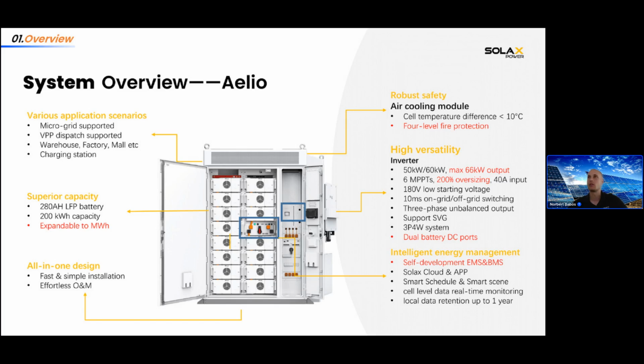And yeah, air cooling with fire protection we will mention in more depth later. With air cooling you have a cell temperature difference of less than 10 degrees Celsius, so it's really just a few degrees. And the inverter, I think we already talked about the inverter. It's good to mention that this kind of inverter has dual battery ports. So if you have an expandable version of the AELIO, you can just connect it to the second DC battery port, and you don't have to have another battery inverter to be able to work together.